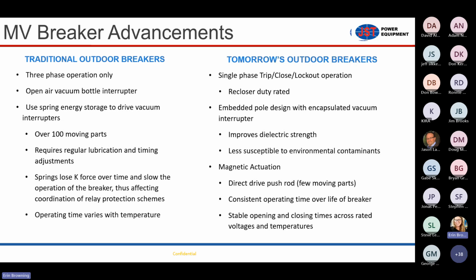As circuit breaker technology evolved, we've gone from oil circuit breakers to air insulated vacuum circuit breakers, and the operating mechanism has again historically been spring energy, where you have a device that has a series of levers and switches and motors that compress springs to store energy, and then once released, that stored energy spring has the force required to open and close a circuit breaker very, very quickly. These types of mechanisms have a lot of parts associated with them. They require regular maintenance, lubrication, and timing adjustments, because over time the springs lose their K force. So the breaker will operate a little bit slower over the course of its lifespan.